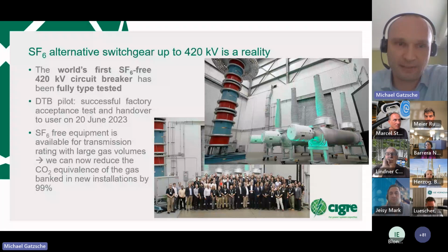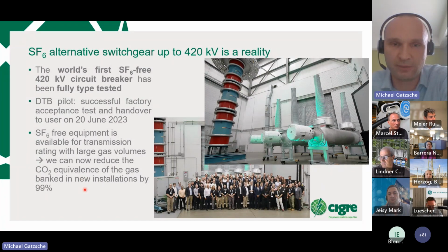With this milestone, we now have SF6-free equipment available up to this transmission range, which is where the large gas volumes are and where we'll see a big increase in infrastructure strengthening in the coming years. Now we have the option to do this SF6-free and reduce the CO2 equivalence of the gas in these circuit breakers in the GIS by 99%.